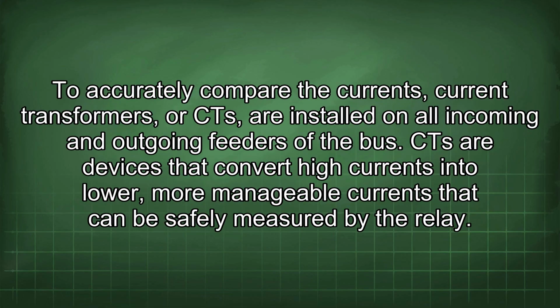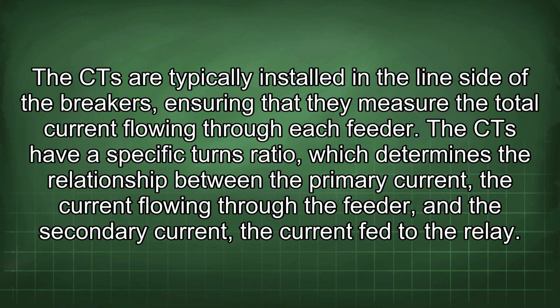To accurately compare the currents, current transformers, or CTs, are installed on all incoming and outgoing feeders of the bus. CTs are devices that convert high currents into lower, more manageable currents that can be safely measured by the relay. The CTs are typically installed on the line side of the breakers, ensuring that they measure the total current flowing through each feeder. The CTs have a specific turns ratio, which determines the relationship between the primary current, the current flowing through the feeder, and the secondary current, the current fed to the relay.